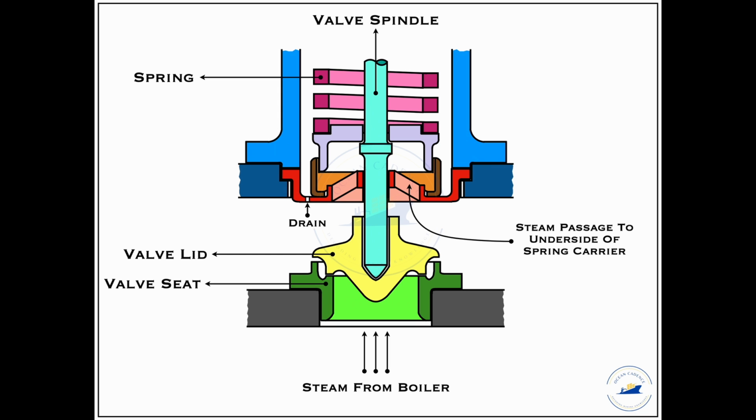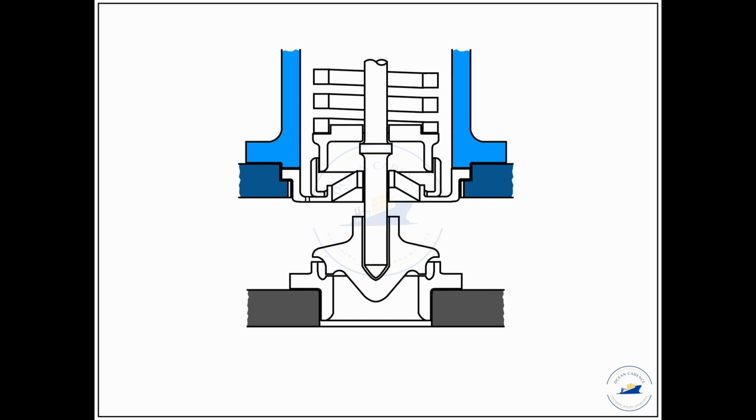So if these holes are choked, then that can create ineffective action of the safety valve, piston, spring, and ultimately the safety valve itself. Also, we have to make sure that there is no corrosive indentation on the body, no salt deposition on the body, and no rust accumulation inside the body and between the other parts that can get trapped and possibly lead to a stuck action of the safety valve.